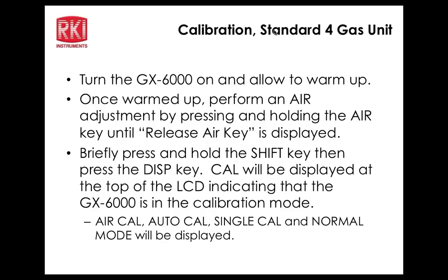Now, is this like the other 2 platforms, like the 2012, where if you don't calibrate all the sensors, it won't reset the date? That's correct. Like the 2012, you have the option of having the date set by the standard 4 sensors or by all the sensors. So depending on which setting you have will decide whether it updates the calibration date if you do all sensors or just the standard 4. Now, on that VOC, does the lamp require it to be calibrated with 100, or can you use 10 ppm to calibrate that lamp, or is that prescribed by Ion Science? You can use a different value, but that's what's in our 5-gas cylinder, and that's also what's in our standard single-gas isobutylene cylinders.